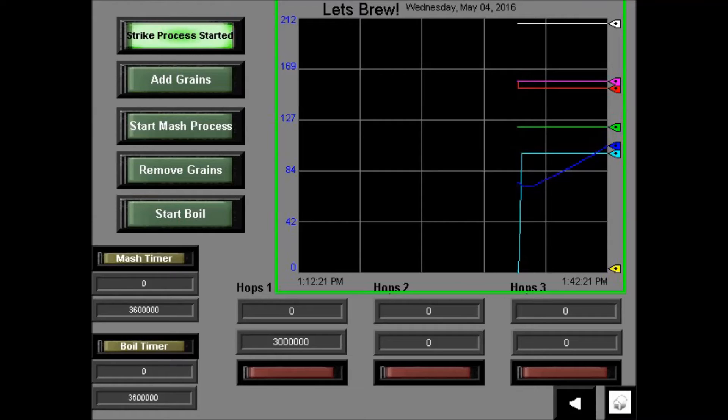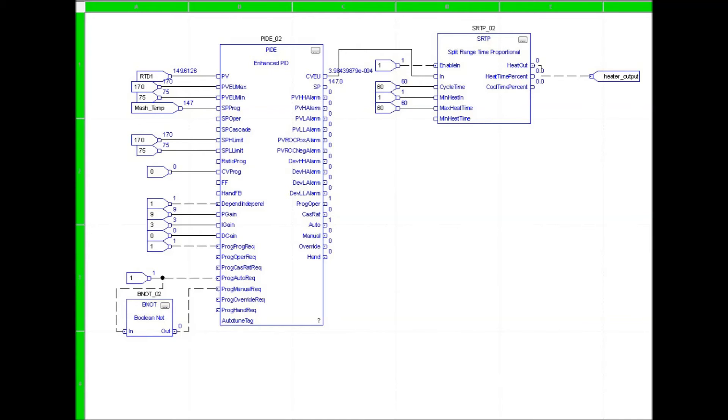Once the user starts a process, the strike subroutine is enabled, and the pump is turned on. The subroutine uses a PID loop that's output is sent to a split range time proportional instruction.